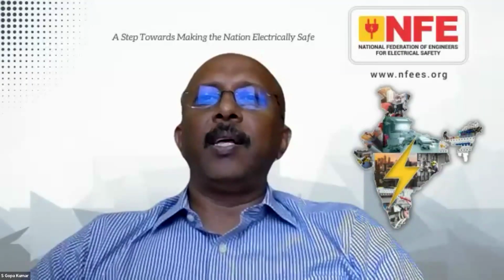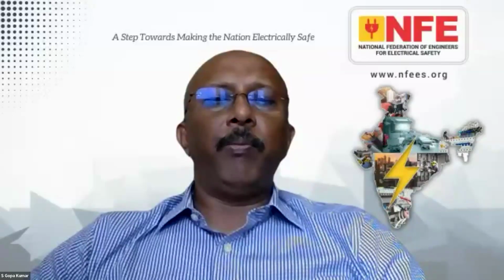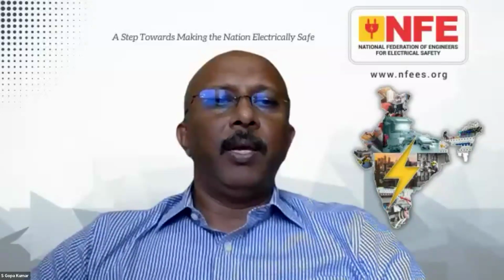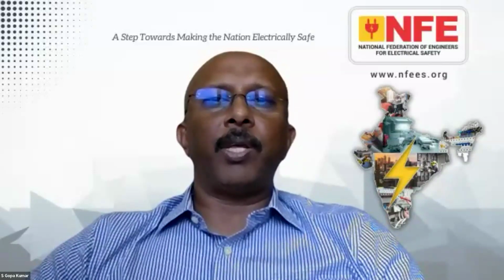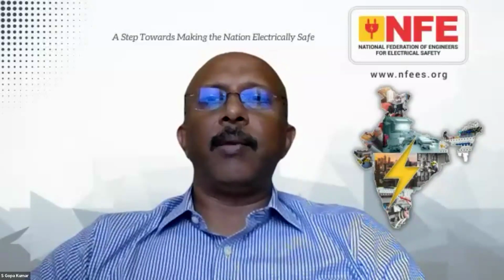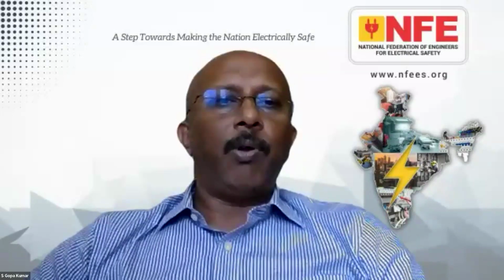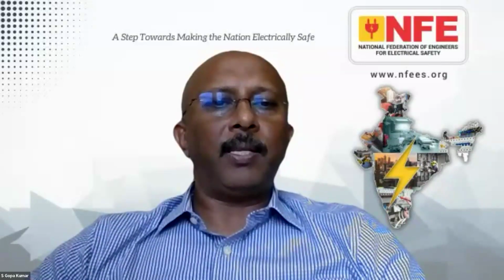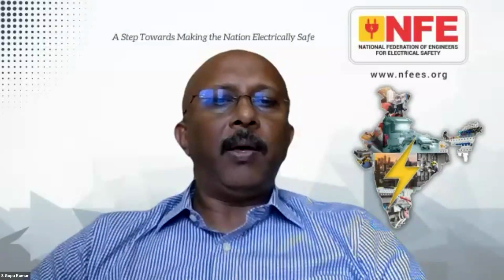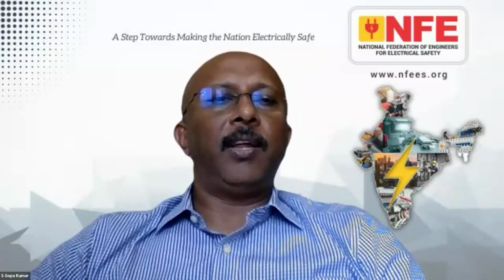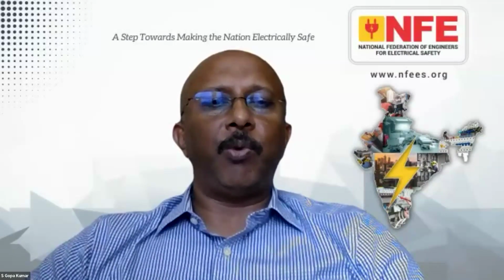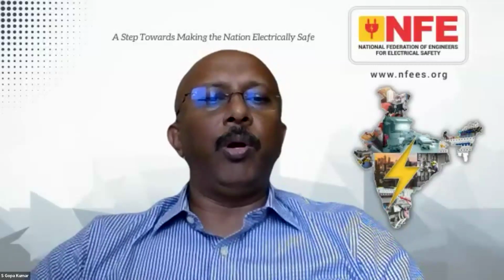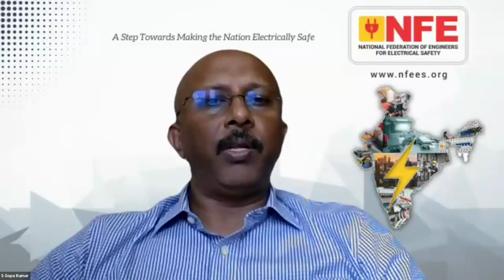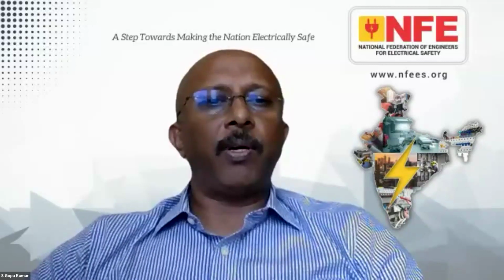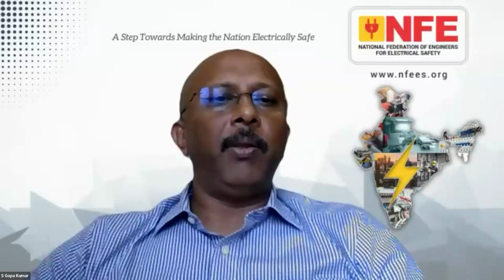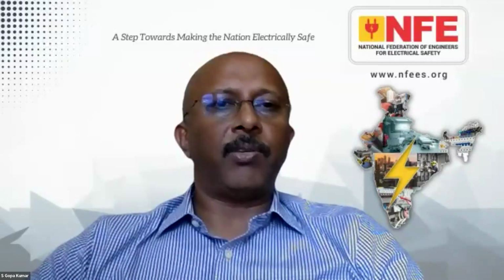Actually, it's a very simple question. I can answer. Most of the time, if you look at earth fault loop impedance, the high impedance is due to non-existence of a fault return path. Instead of a metallic fault return path, we provide two or three earth electrodes, and basically all the connections are corroded or have loose contacts. As a result, impedance is high. In line to line, most often the wire sizes and circuit protective devices are oversized. Similarly, the joint resistances are also too much. Instead of making the connections with a very small resistance, most often the connections look good externally, but we don't have the habit of checking the resistance of each and every joint. For example, certain applications need a joint resistance of 10 milliohm, but practically it may be 100 milliohm, because we don't check. So basically it is the loose contacts and the non-existence of a fault return path.